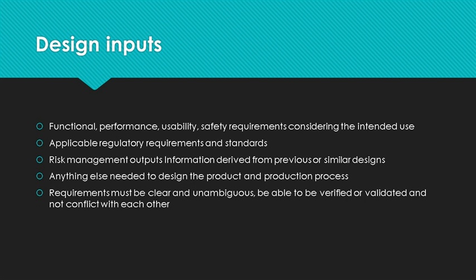After the project is planned, and frequently in conjunction with planning, the design inputs need to be defined. This is a place to ask customers what they want and to look at supplier surveys. Inputs should include functionality, performance, usability, safety requirements, and consider the intended use. Now, that's very important. It's the intended use, not the possible misuse. Inputs should also include applicable regulatory requirements and standards. This is actually in both ISO 9001 and 13485.